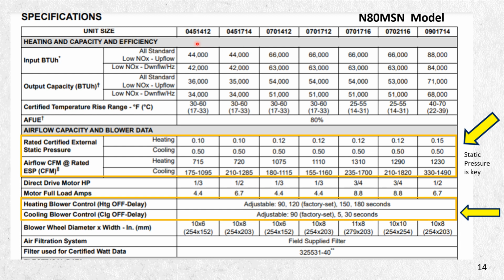So if you were reading this chart up here, it would be 045, that's 45,000 BTU, 14-inch cabinet, 1,200 CFM, 17-inch cabinet, 1,400 CFM, 70,000 BTU, 14-inch cabinet, 1,200 CFM. So you can read it like that to understand where you're going to be on the CFM factors. And this is that heating blower control off delay that we talked about. It comes in 90, 120, 150, 180. It's preset from the factory to 120. And then your cooling has 5 and 30 seconds. It's factory set at 90, so that can be adjusted.